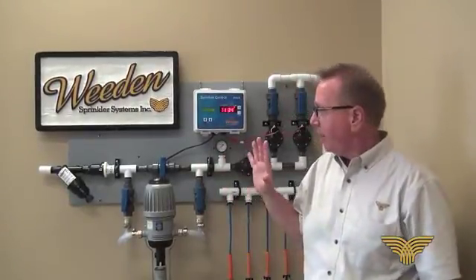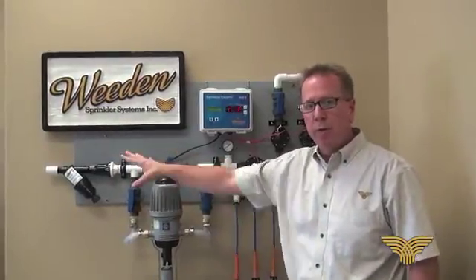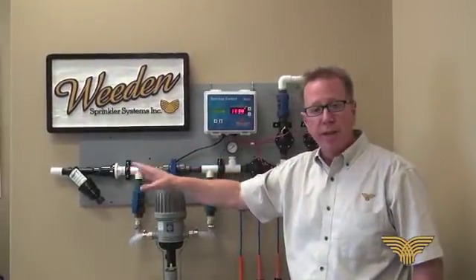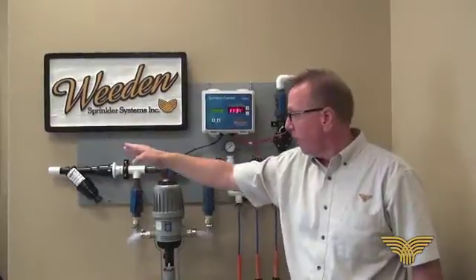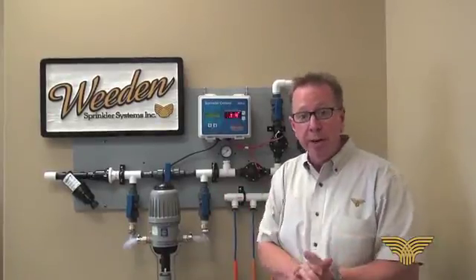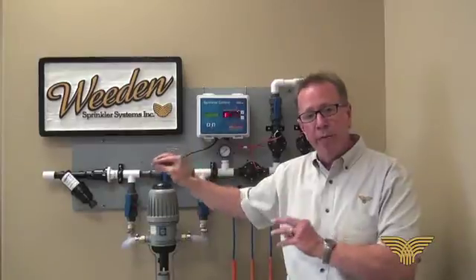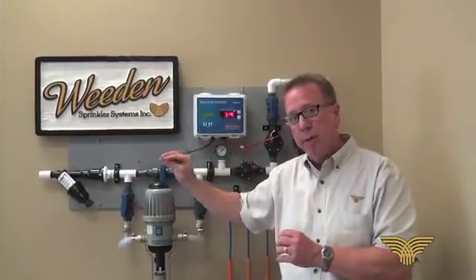This is a demonstration unit for a Weeden Sprinkler Systems. Starting on the left side where the water would be coming into the manifold, the first thing we see is the filter. It's a stainless steel 100 mesh filter, a flow-through filter. It does need to be maintained — based on their water quality, growers may have to flush it out once a month, once every six months, or once a year. It'll take out any particle that would ever plug a sprinkler spinner.